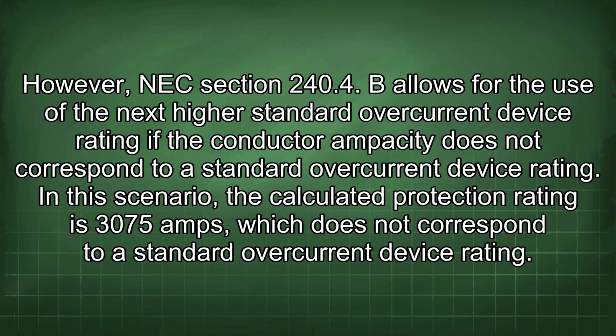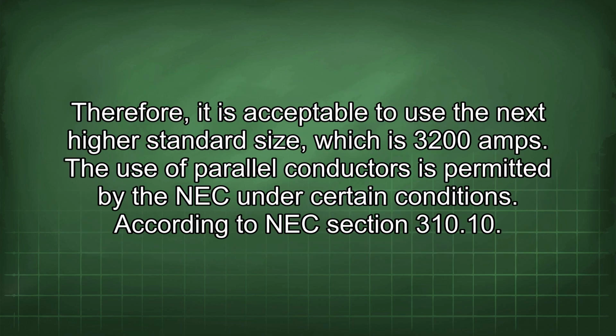However, NEC Section 240.4(B) allows for the use of the next higher standard overcurrent device rating if the conductor ampacity does not correspond to a standard overcurrent device rating. In this scenario, the calculated protection rating is 3075 amps, which does not correspond to a standard overcurrent device rating. Therefore, it is acceptable to use the next higher standard size, which is 3200 amps.